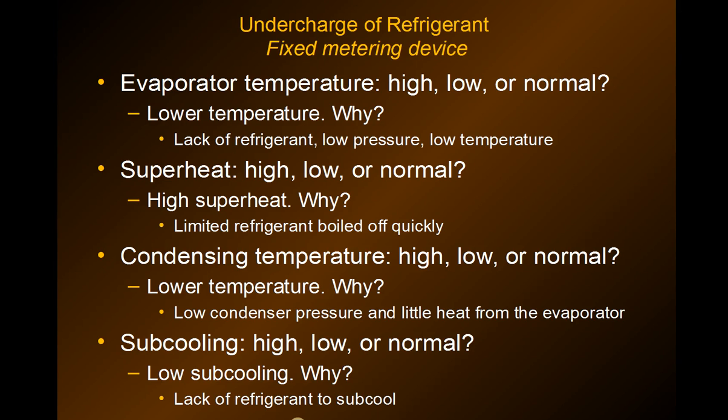You need to explain the situation to the restaurant or store owner, reclaim that refrigerant, weigh in the factory charge, and start fresh. Because if you don't, you will spend hour after hour looking for a problem that may simply be caused by low refrigerant charge. If you do a leak search, you're not going to find a leak — if the previous technician had put his gauges on two or three times, that critically charged system is going to be low on refrigerant.